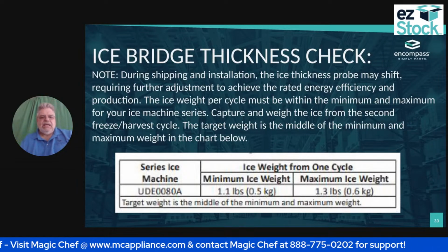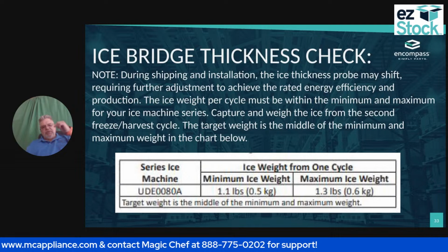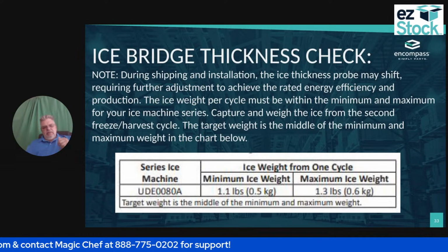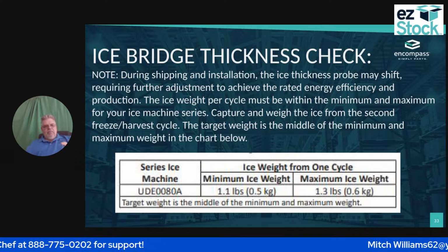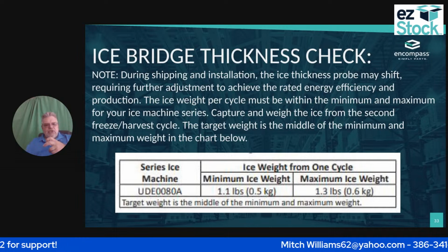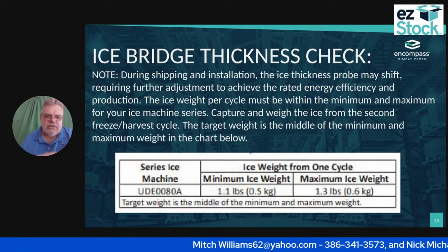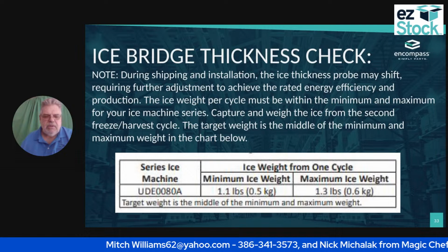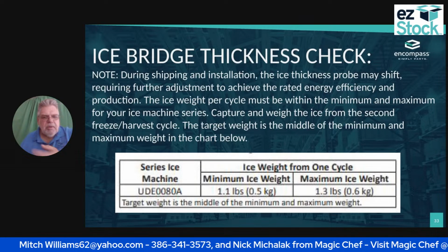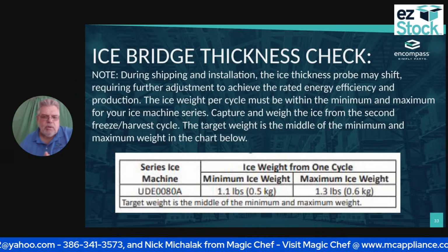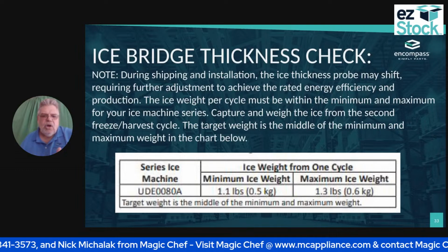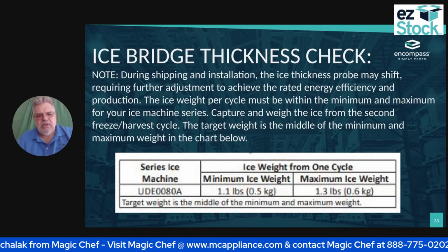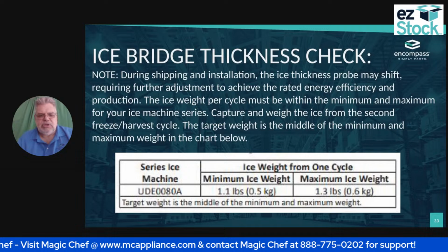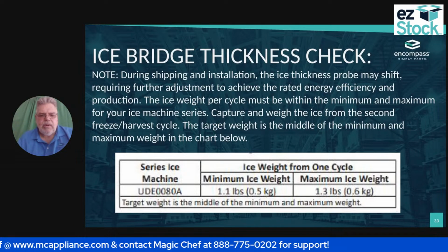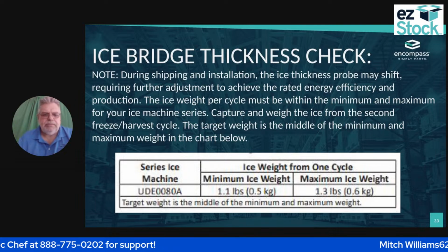Okay. Ice bridge thickness. It comes pre-checked from the factory. Okay. And it should always be exactly the same. So my minimum ice weight should be somewhere between 1.1 pounds up to 1.3 pounds. So this ice machine produces 1.1 to 1.3 pounds of ice with every drop.